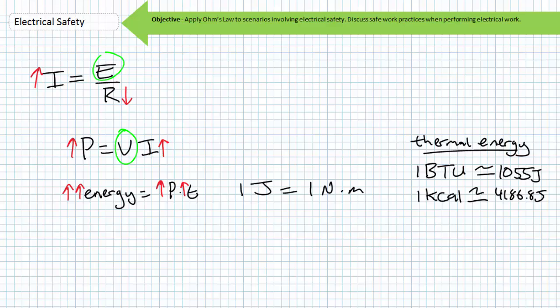This does not mean you don't have to follow proper lockout and tagout procedures, but it does mean you have an extra level of protection when the PV array isn't energized. Step 2. Don't be a low resistance path. An insulator needs to be between you and high voltage sources. Make sure your listed personal protective equipment is dry and passes daily inspection. A common piece of personal protective equipment associated with electrical work are rubber gloves. Rubber has a high resistance. Rubber is an insulator.